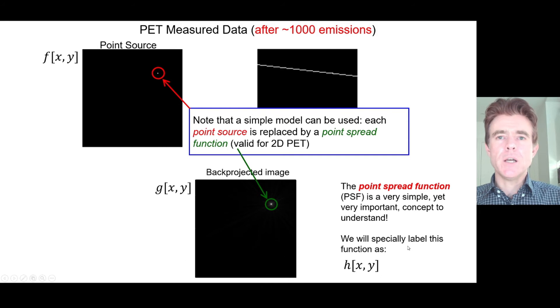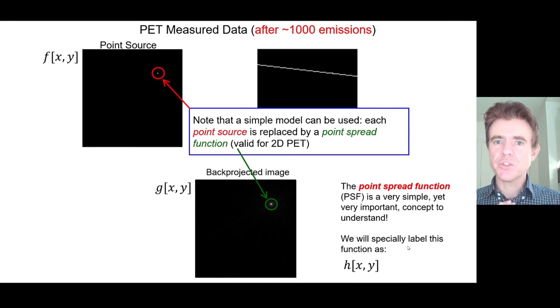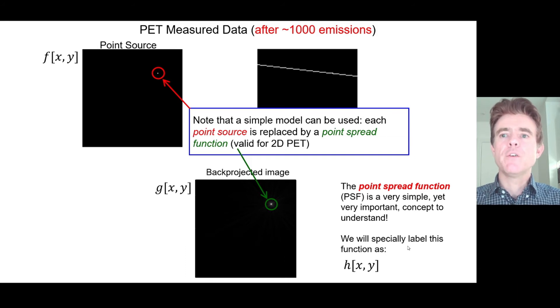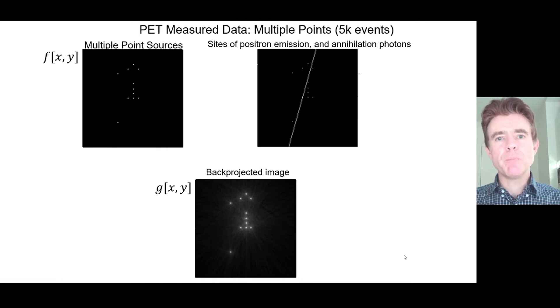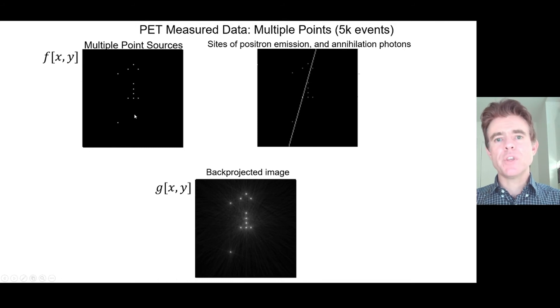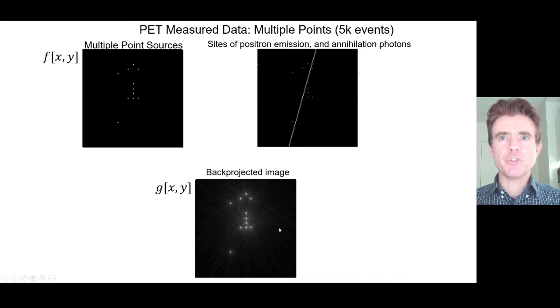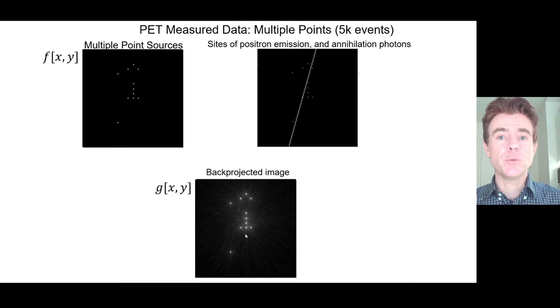This is already building up a picture of what convolution is doing — there's a substitution process going on. A point source has been replaced by a point spread function. As we build up complexity in our 2D image, with multiple point sources inside the scanner field of view, we do exactly the same process. After around 5,000 such back-projections from all those point sources, we get lots of different point spread functions. The key point is that with this geometry, they are all the same shape — just differently positioned.